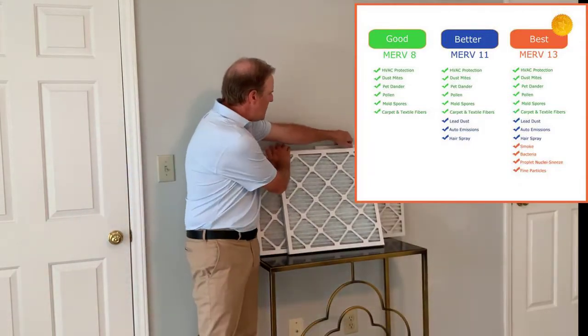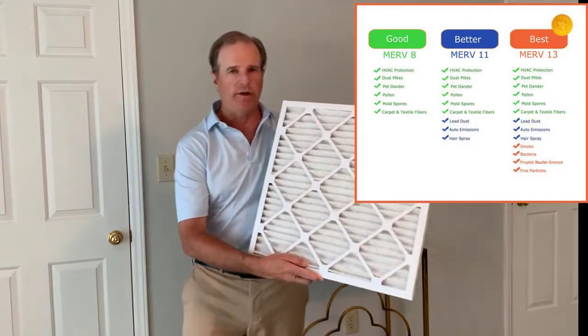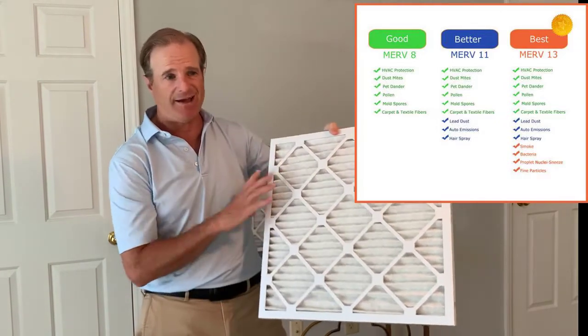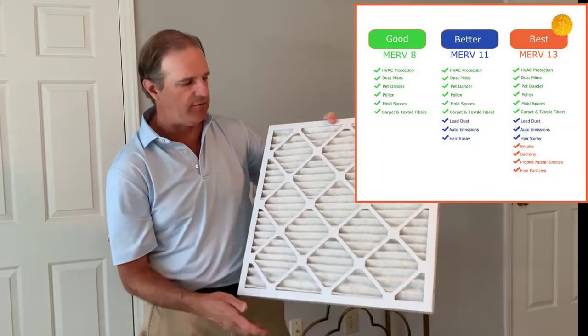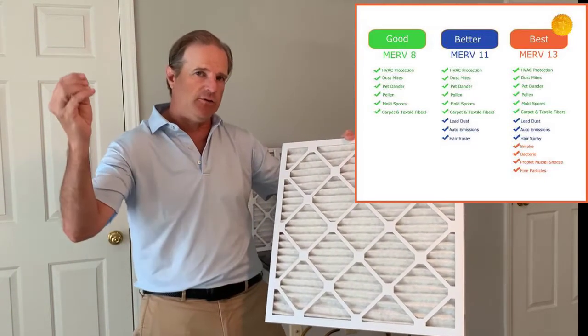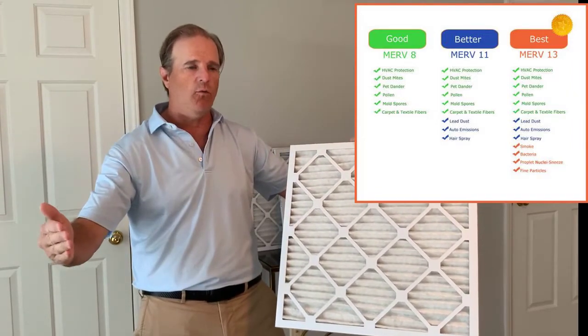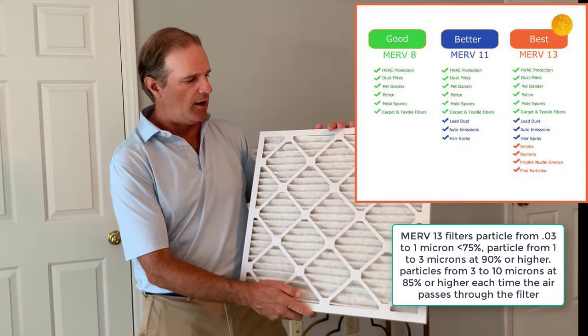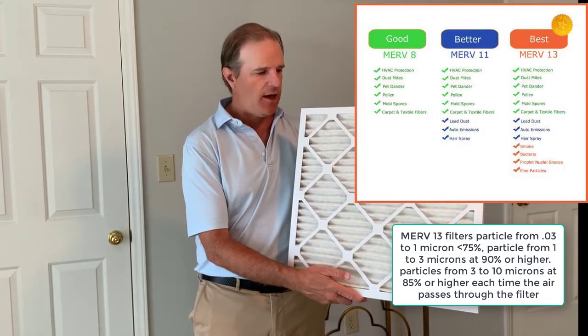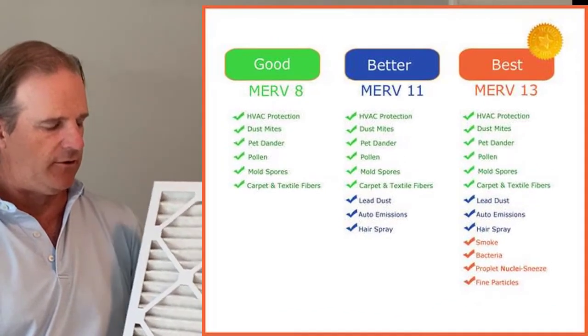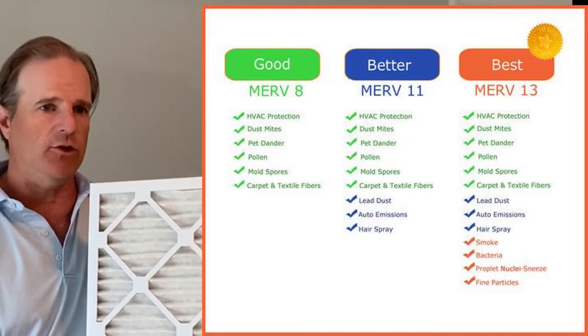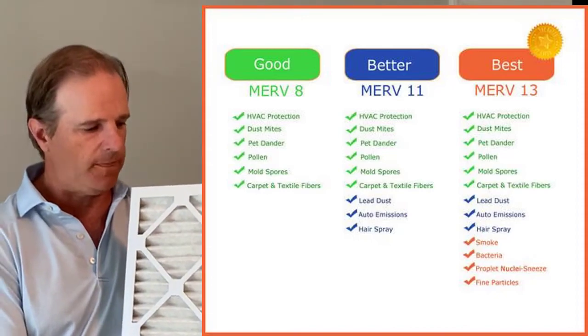The last filter is MERV 13, generally the highest level you'll find in a one-inch filter. It's used in high-end residential buildings and hospitals. MERV 13 filters down to the size of bacteria and viruses — down to 0.3 microns. From 0.3 to 1 micron, it filters out a large percent of particles every time air passes through. This is great for allergy sufferers and is generally the highest filtration level available for a one-inch filter in most residential buildings.